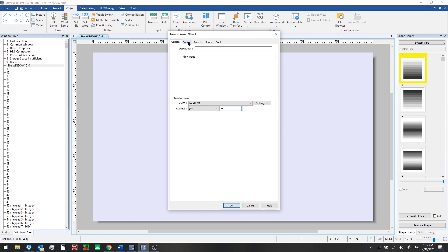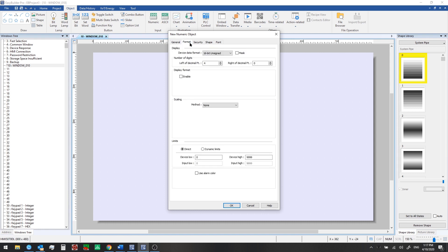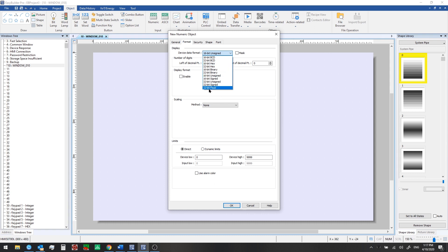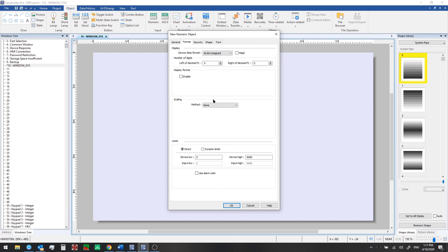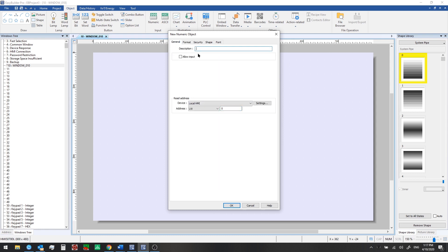If we go to the format tab, we can see there is a data format option. So 16-bit unsigned is the default, but you could select from other formats like 32-bit float, for example. You can set the number of digits left or right of decimal from this area. And you can configure limits and scaling here, which we'll look at in more detail later. For now, we'll just go ahead and add this to our window. So we'll click OK.